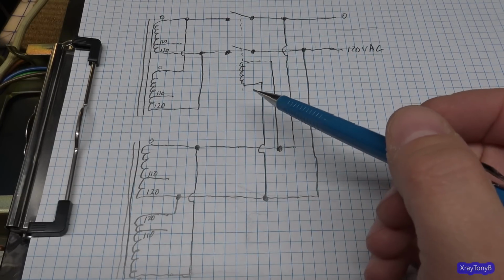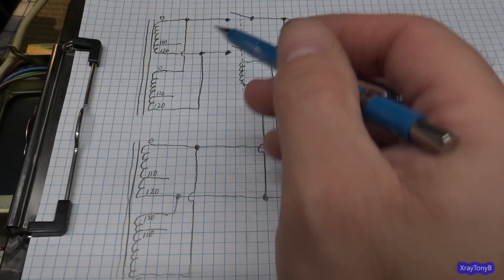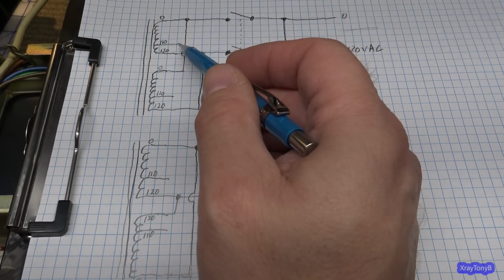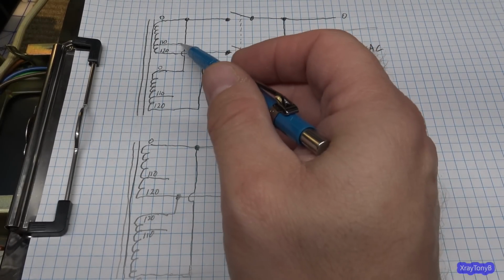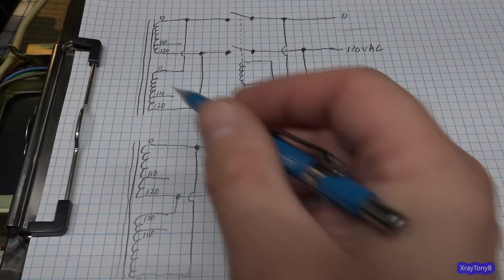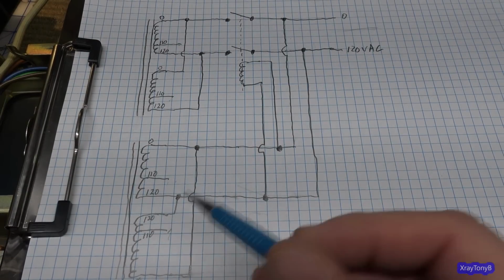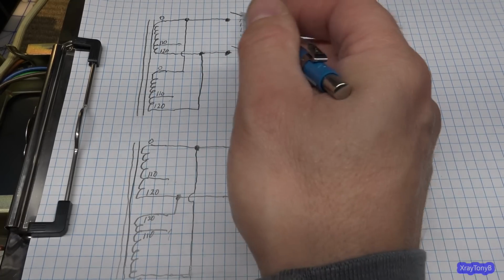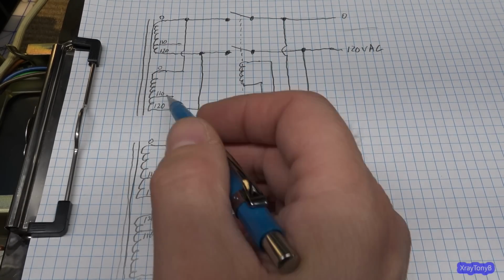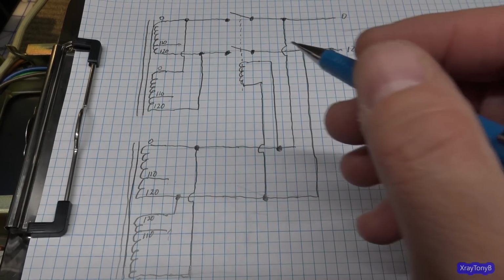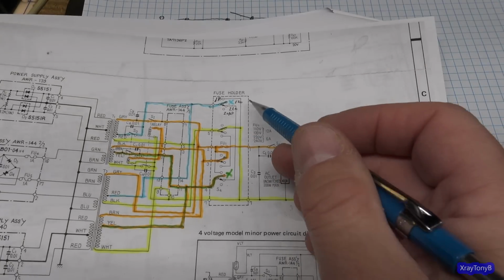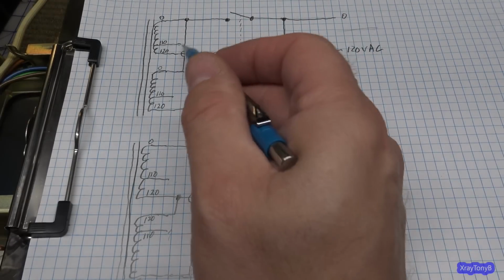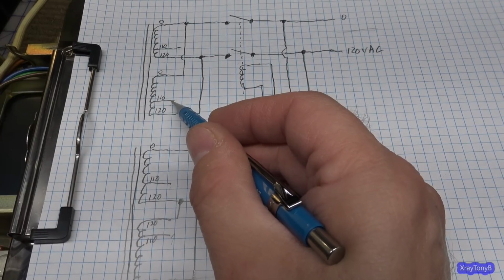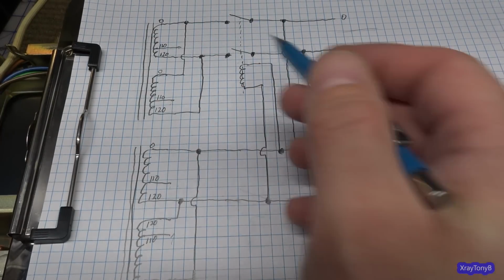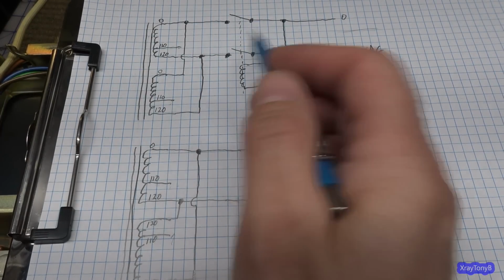Now that other relay, the reason there's a second one here is they put this same set of relays here and here. This one is tied to here and this one is tied to down here. And then they put a relay like this on both of these, so that if you have it jumpered for 110 volts, it switches this on and off instead of this one, and this one becomes not connected to anything.